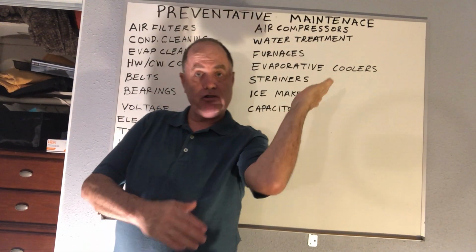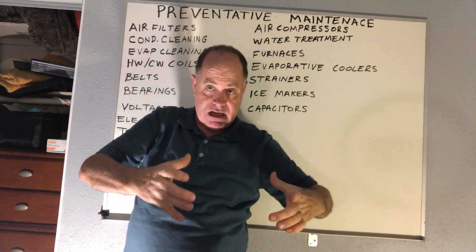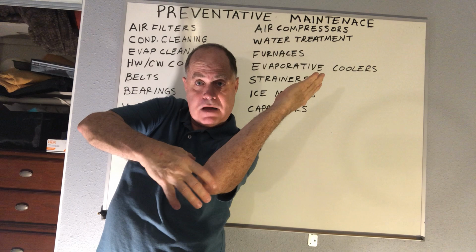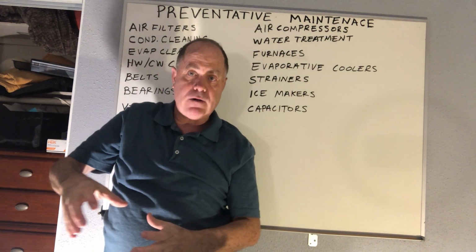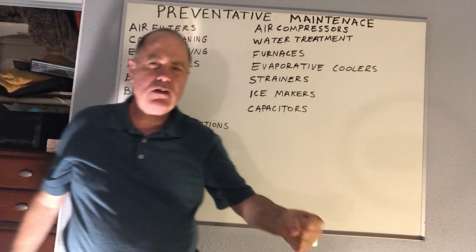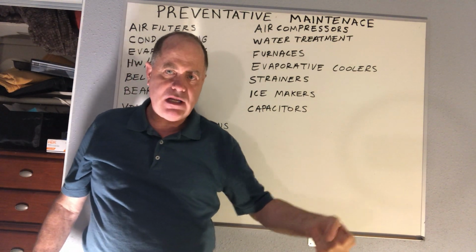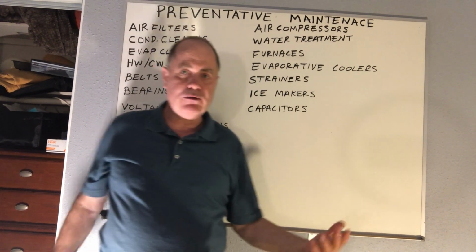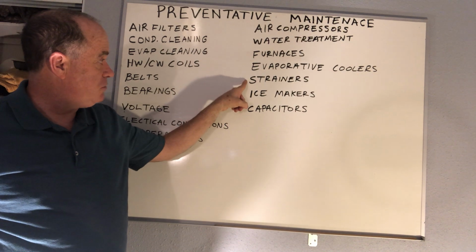Right before your condenser water pump, you may have a big steel pipe like this coming in to your water pump, and you'll have a 45-degree strainer that goes into the piping. You can take the cap off and pull that out, and then you have this strainer that needs to be cleaned, okay? You can also sometimes, mid-season, hook up a garden hose to that and do a flush on it, which will help keep it clean until you are able to remove the whole thing, okay? So that's a tip on your strainers.